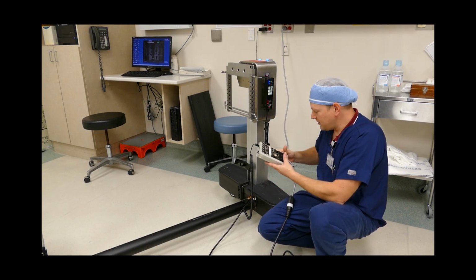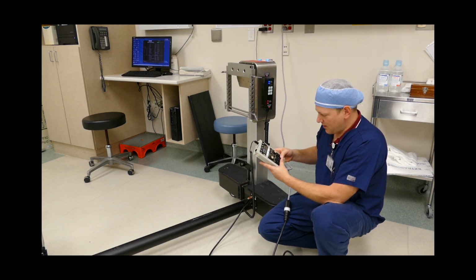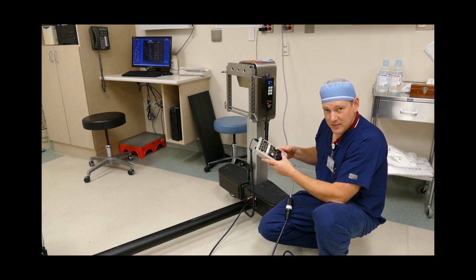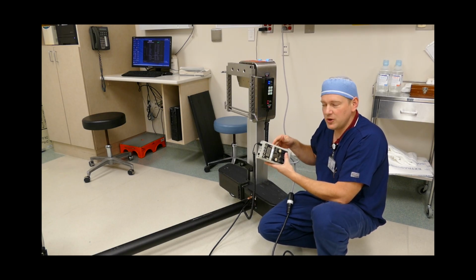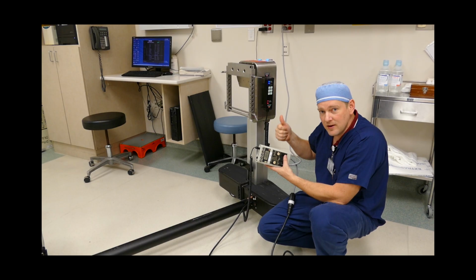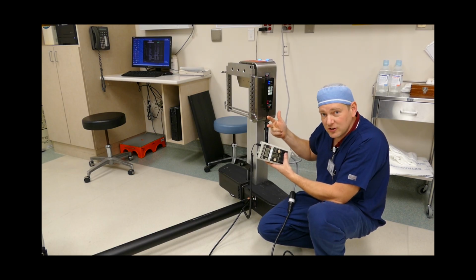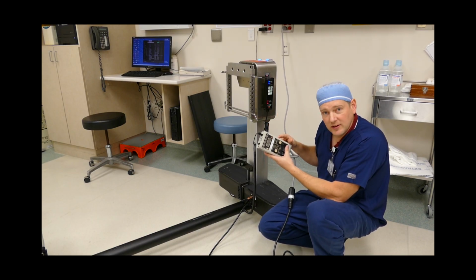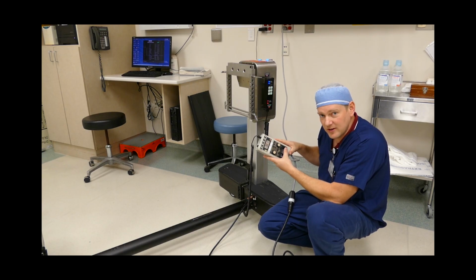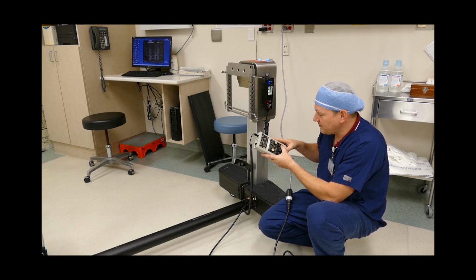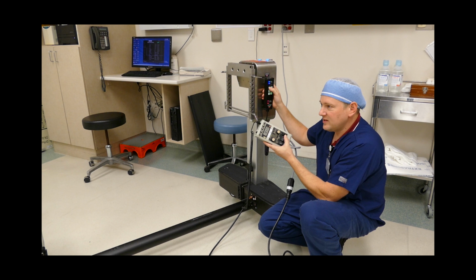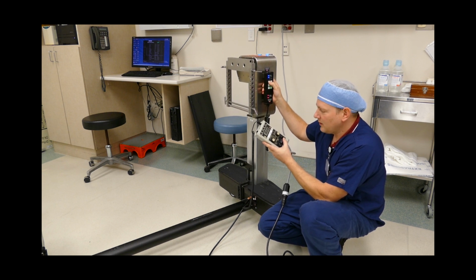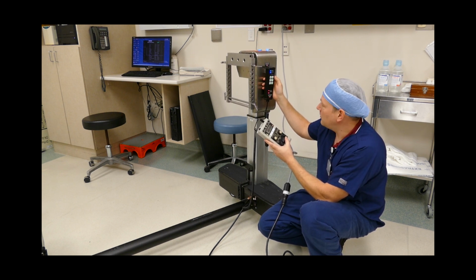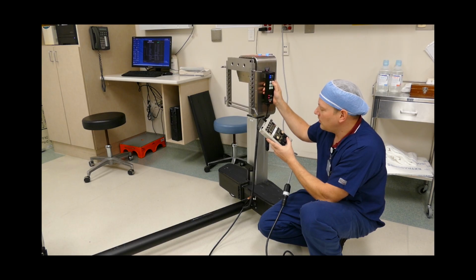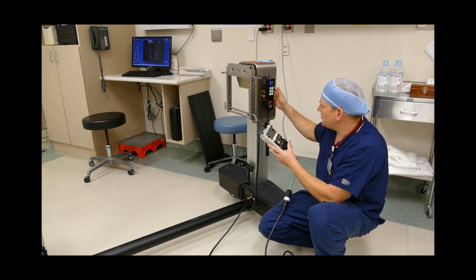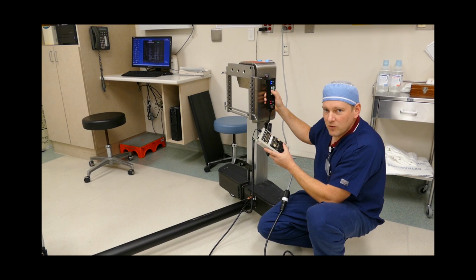Ensure that the power is on. I'm going to lift ground and I've got 11. Here's the trick. You have to make sure that you run each and every fan, motor, or heater chiller while you're doing the leakage test to test whether or not it's actually giving out leakage. I'm going to lift ground and I'm going to raise the table. I've got 12 microamps is about what I'm getting, but then we have one other motor.